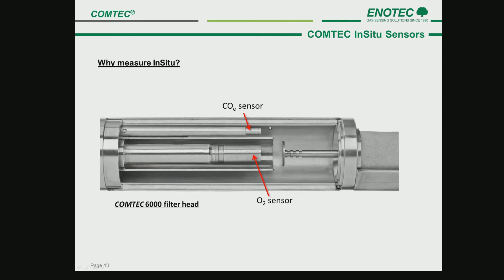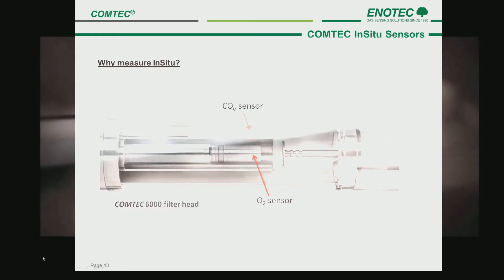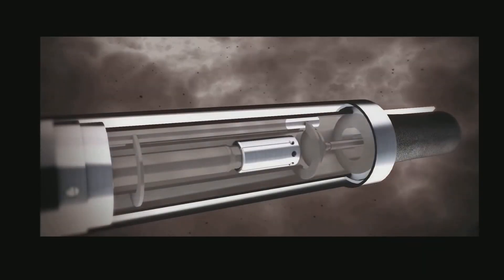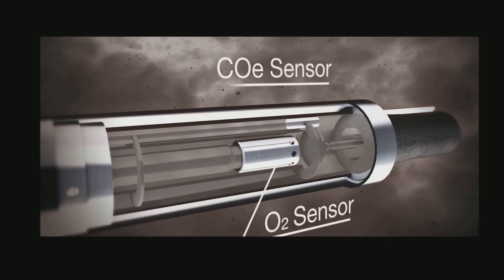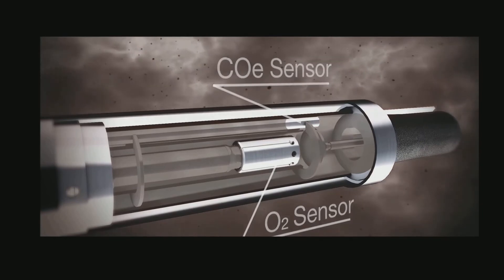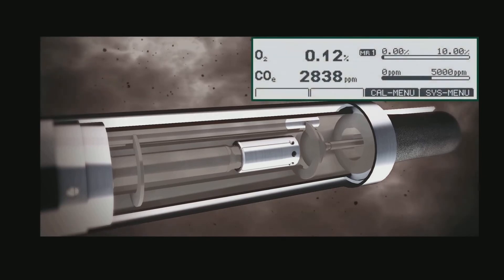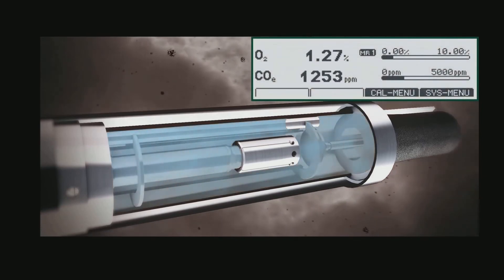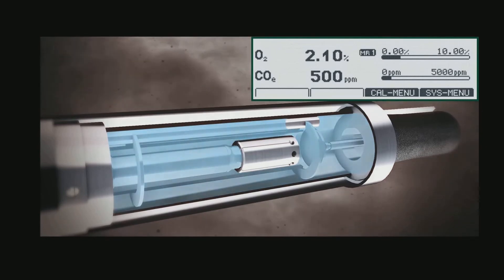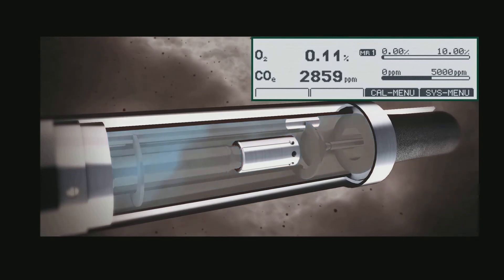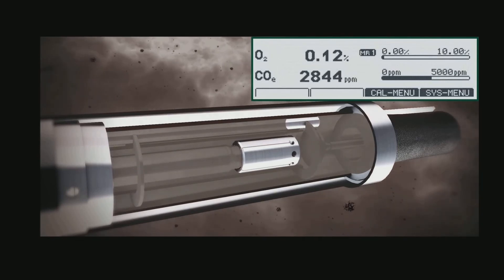This is a sectional view of the Comtec filter head. Here the COE sensor and the O2 sensor can be seen directly behind the diffusion filter. This video shows a Comtec sensor verification taking place. First, one can see the filter head filled with process gas surrounding the sensors, and the measured values can be seen. Test gas is applied directly from the controller, which includes a full pneumatic system. Test gas displaces the process gas very quickly and the test gas bottle values are reached. The measured values are proven to be true. The test gas is switched off and the process gas is once again measured.